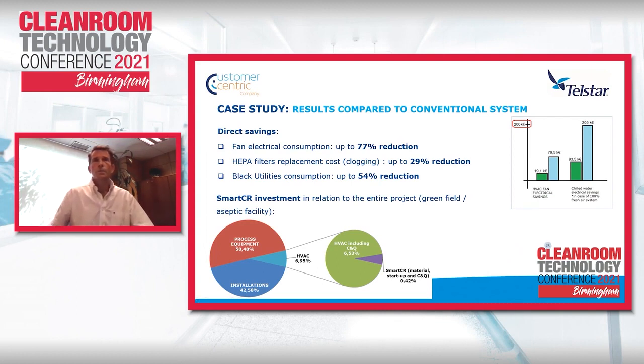At the end of the day, what we evaluated in these case studies was that the fan electrical consumption was reduced by up to 77%. For the HEPA filter replacement, this was an estimation together with, I think it was, Canfield, up to 29% reduction of cost, and black utilities will also reduce by 54% of cost. Black utilities will depend very much on the placement and on the strategy of the HVAC. Obviously, if we are talking about 100% fresh air, the opportunity for cost reduction of energy consumption is bigger than if we have 10% fresh air. If we have a location with high temperatures or humidity, the savings opportunities are also much bigger.